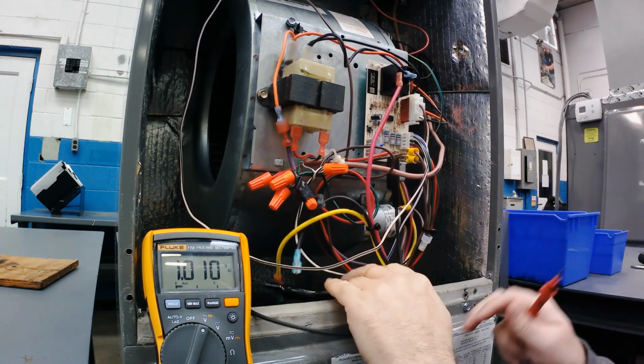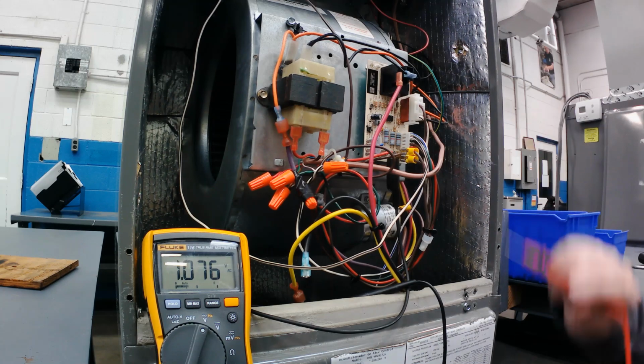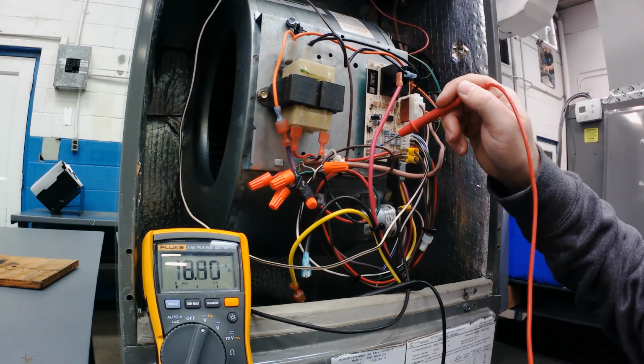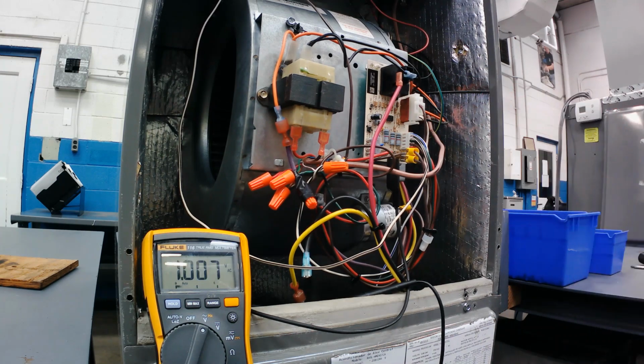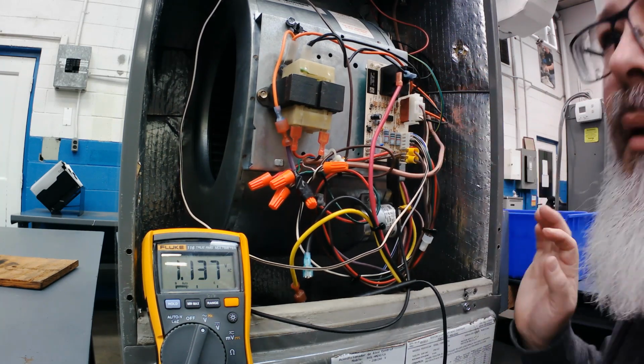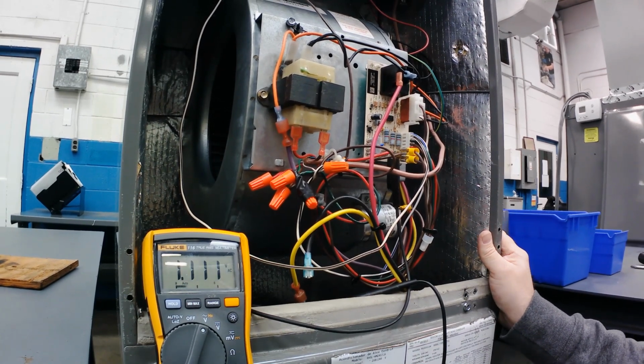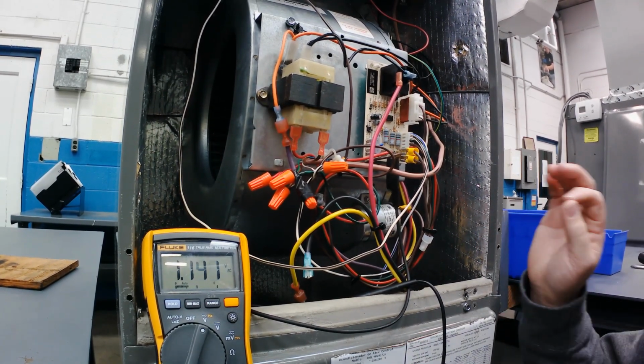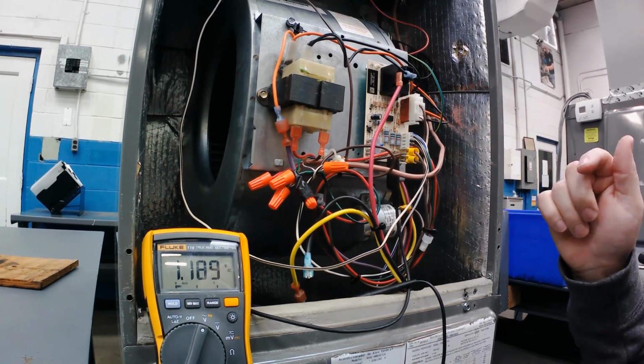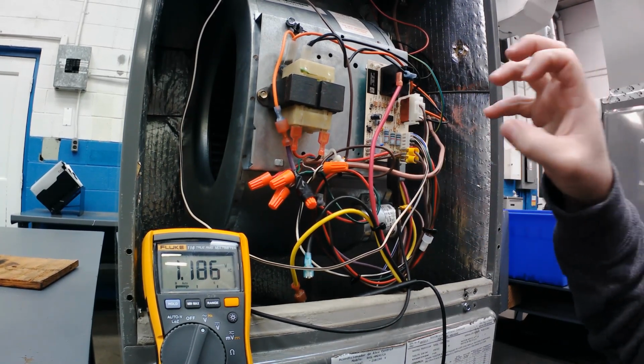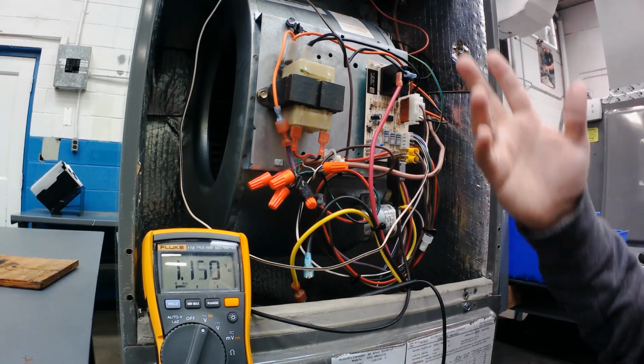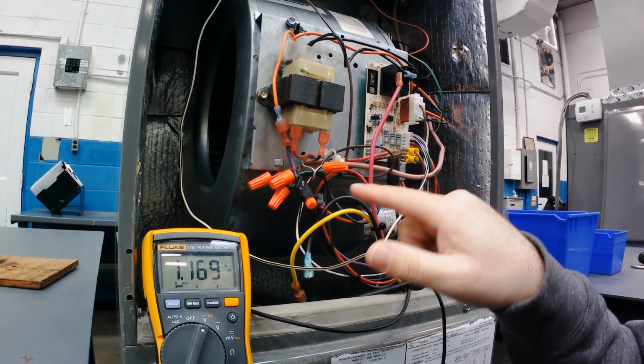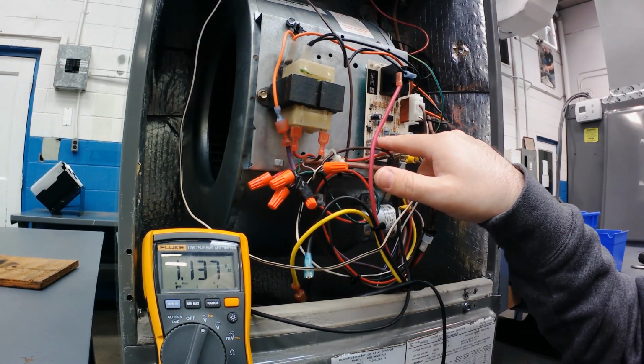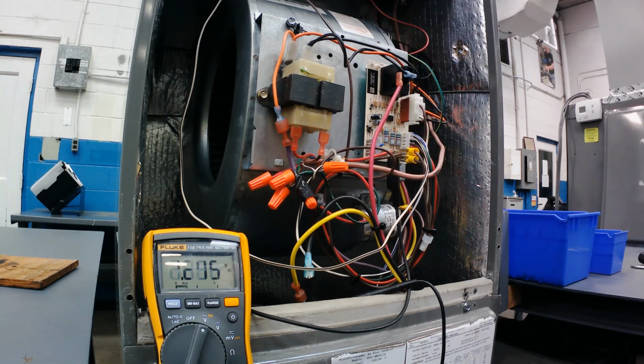Okay, so anytime I'm checking voltage now and I'm following the hot circuit, the R into the board, then into the fuse, then out of the fuse. Okay, you can remove this plug and check certain things. You have to be mindful of what you are checking. So if I was going to check power, I could easily pull this plug and check R, and since my alligator clip is on the constant always, or on the common always, then I should get voltage, or I would see if the board is actually allowing power from the fuse across the board so it can go to my thermostat. But a lot of times when you unplug the plug, there's other things later that don't work.